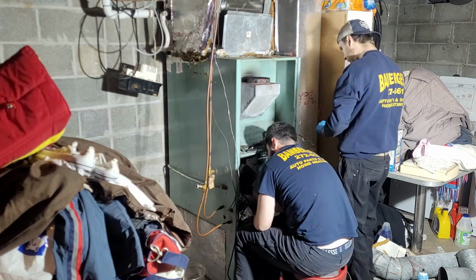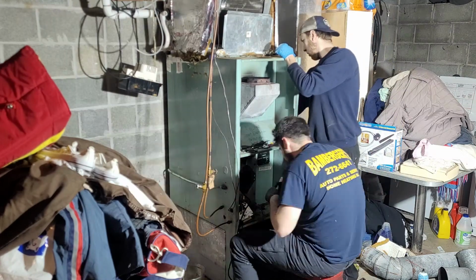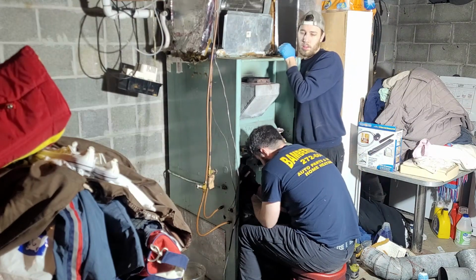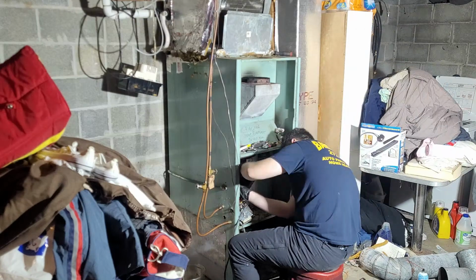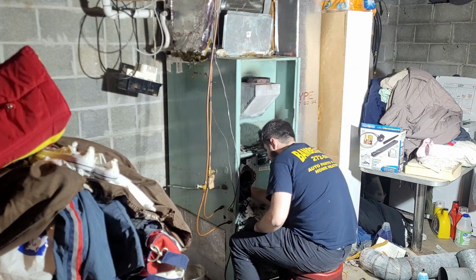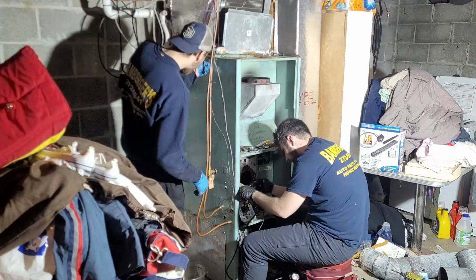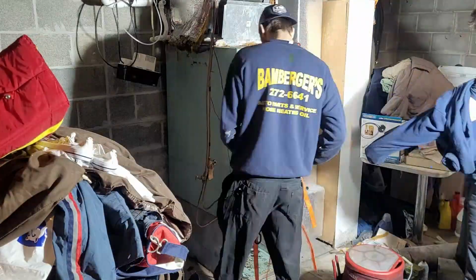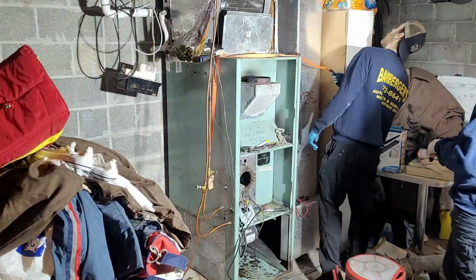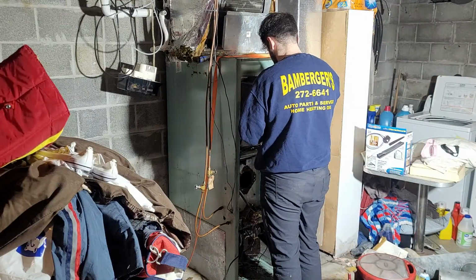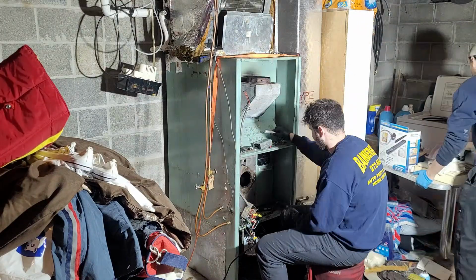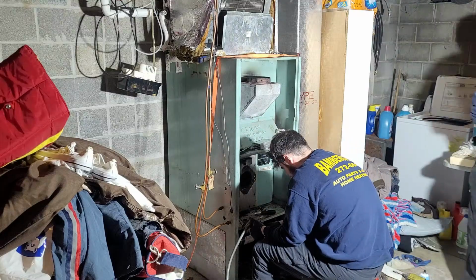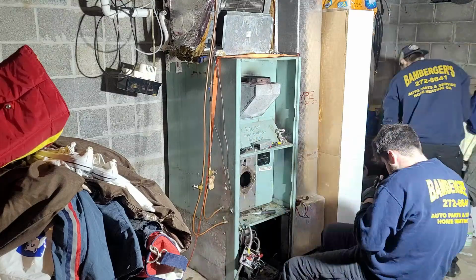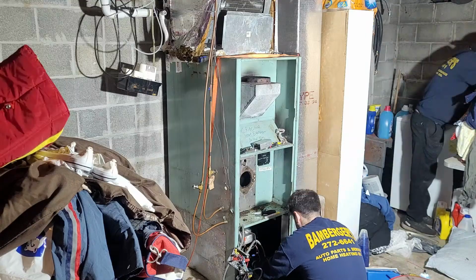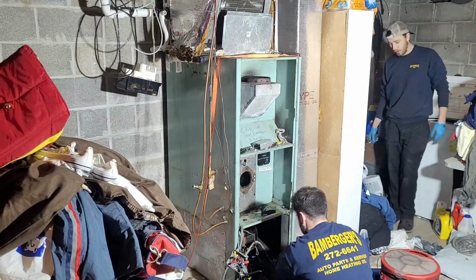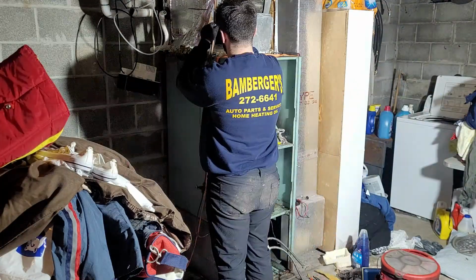While we wait for the next part: if you're replacing a furnace that has an oil burner and plan on using the same burner, make sure it's compatible with the new furnace, because they're not all the same — settings and nozzle size do matter. You might need to change some settings or the nozzle if keeping the same burner, but we'd recommend getting a new burner along with a new furnace.